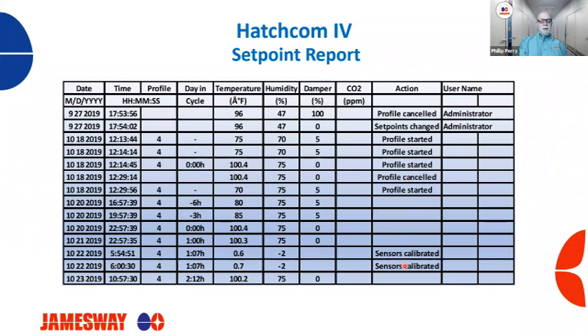Down here, we see the sensors were calibrated at 1 day, 7 hours. And then they calibrated twice here, so there were two changes. If they do not do a sensor calibration, but they check the sensors for calibration and there's no value change, then it doesn't record this action. So we'll just have to rely on it: if someone says they changed it, calibrated, you can cross-reference here to make sure they have done it.